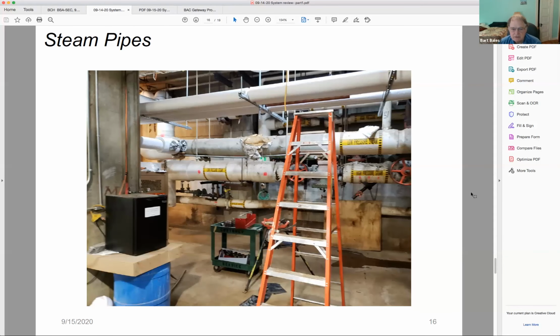Just showing that they have both high and low pressure steam delivered to the building, at least in the original design. The person taking us around indicated that they were operating all on low pressure steam. Now, we haven't independently verified that, but that's what we were told. And they're using steam to make hot water, for hot water being distributed around the building, and then the chillers provide chilled water for going around the building. And this steam is from a district steam sent from elsewhere. It's not made in the building. Okay.